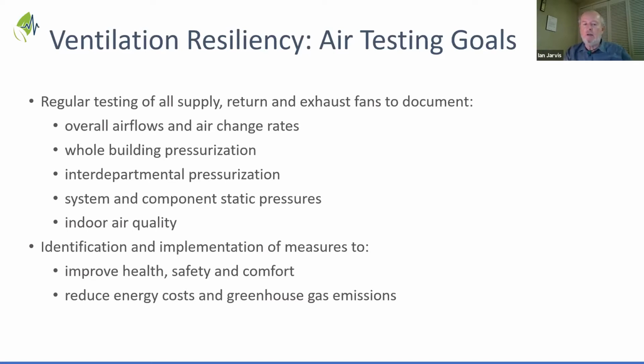Then once you've got the whole building under the right pressure, there is the relative pressurization of adjacent spaces, so you have the right positives and negatives throughout. That is a necessary outcome to, again, provide assurance that that is the case. Coming out of your testing work, we'll talk a lot about static pressure losses within the system and what they're trying to tell you and how you can make improvements that can lead to dramatic electricity savings. That's where fan power is the biggest electricity user, I think, in every one of your hospitals. Getting after static pressure can actually allow you to provide greater airflows, but at significantly lower fan power, which is the big reduction. And we'll talk a lot about what the metrics of indoor air quality are that you could and should be tracking and reporting on, so that everybody, again, has the comfort and the confidence that the building is healthy and safe, which is what it has to be.